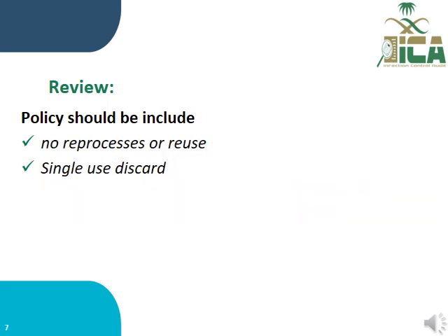Also, the policy should include that single-use devices should not be reprocessed or used again, even for the same patient. And it should be mentioned that disposable single-use devices that have been opened and not used should not be reprocessed or re-sterilized. It should also mention how to discard single-use devices: they should be discarded by the end user at the point of use as per hospital protocols.